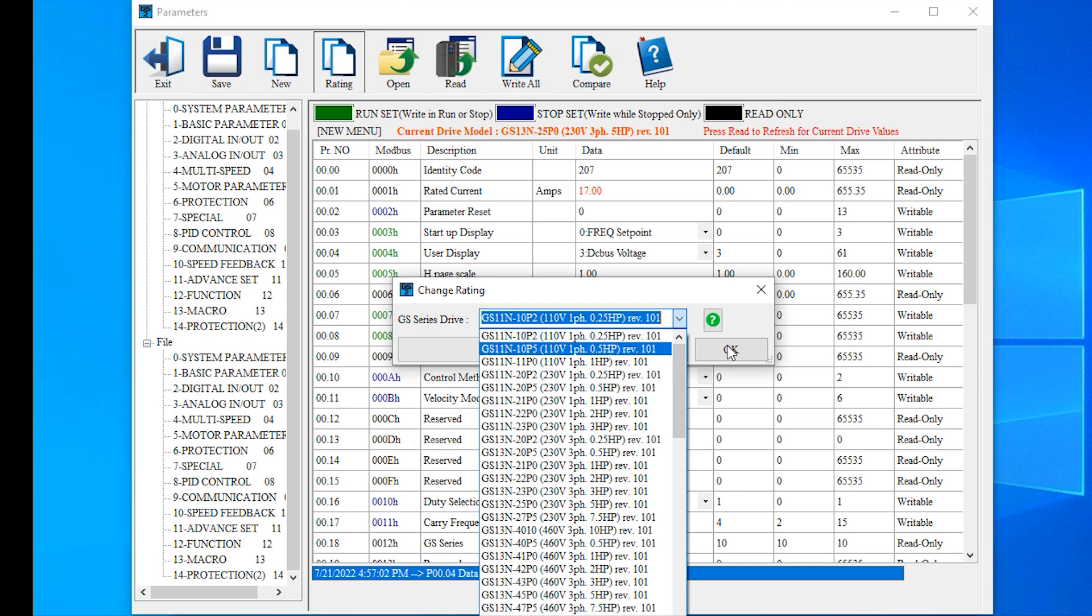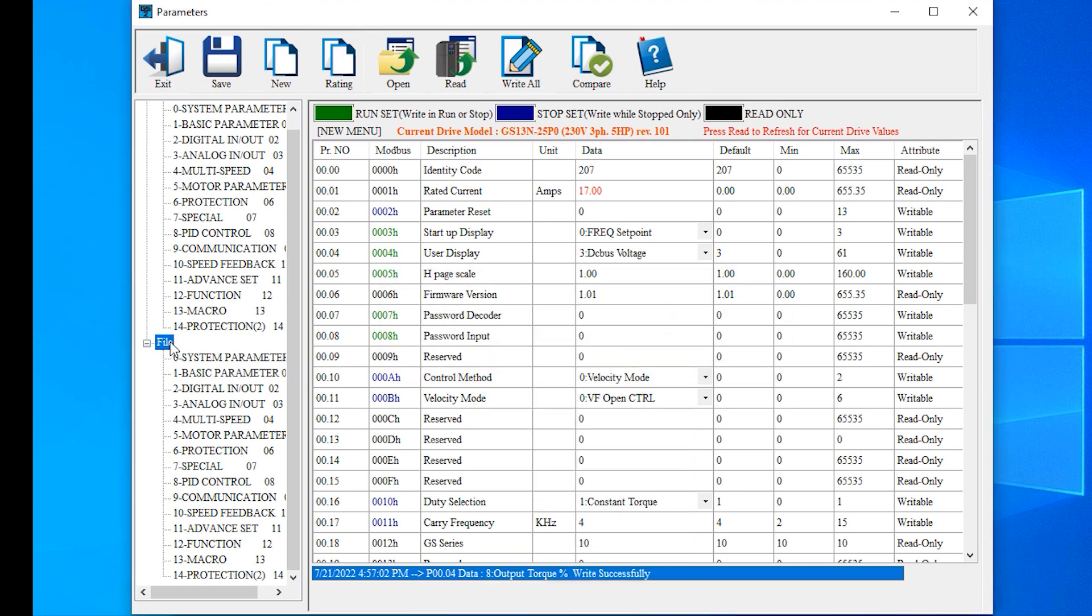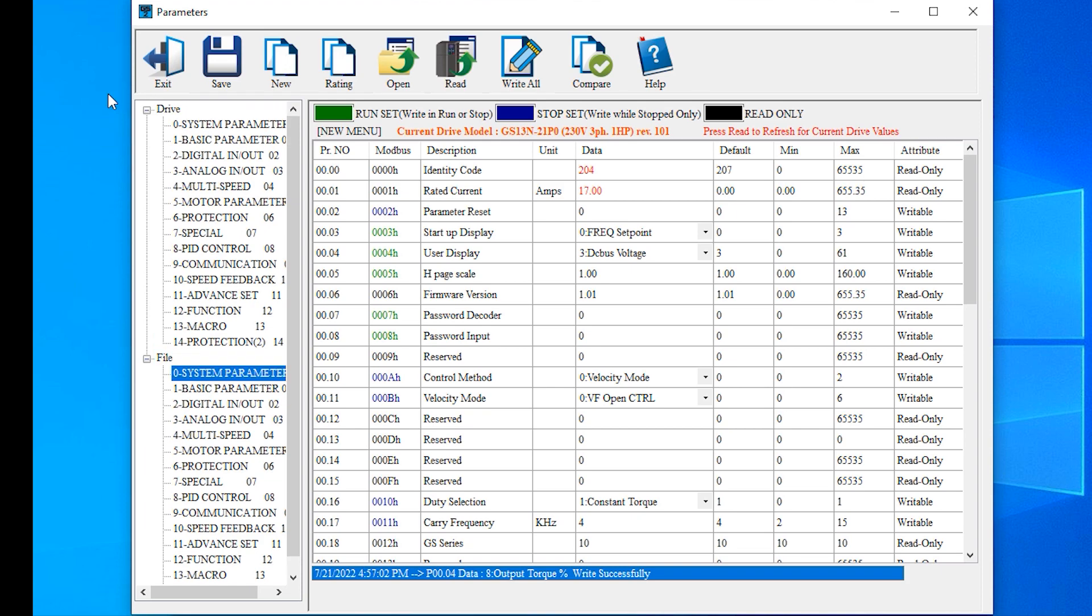Again, this is a file operation, not a drive operation, so make sure you write to the drive. One thing to keep in mind, if you are trying to change to a GS-20 set up for GS-2 mode or GS-4, ratings will allow you to change the drive model but will not preserve the parameter settings because the parameter set is too different.